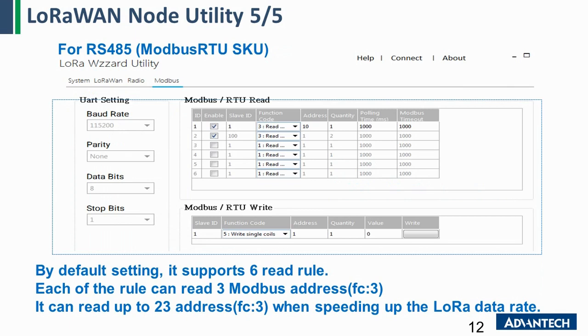This is the settings page for the RS485 SKU. You will have the UART setting to connect with your sensor, and you will have 6 Modbus read rules to communicate with your Modbus sensor. Each rule can read 3 Modbus addresses under function code 3, but it can read up to 23 addresses when using a higher LoRaWAN data rate. Configure the rules based on your application.